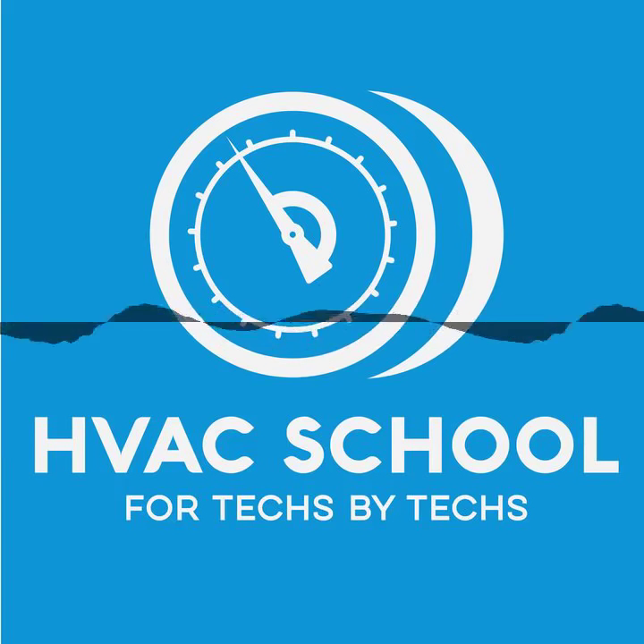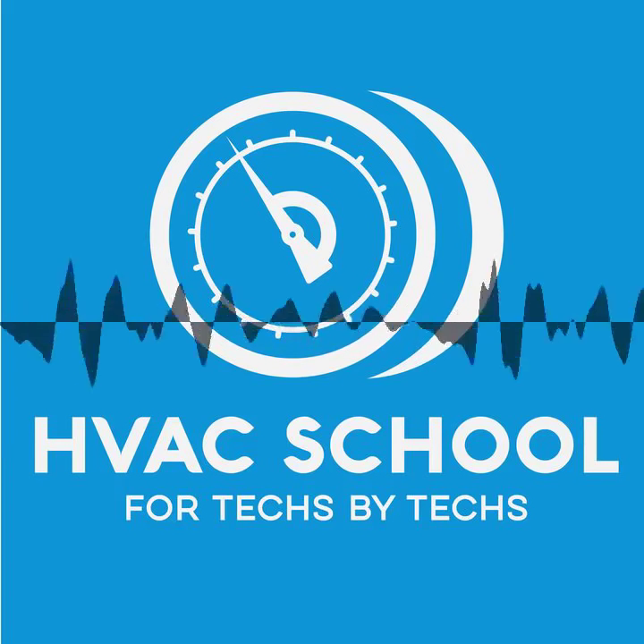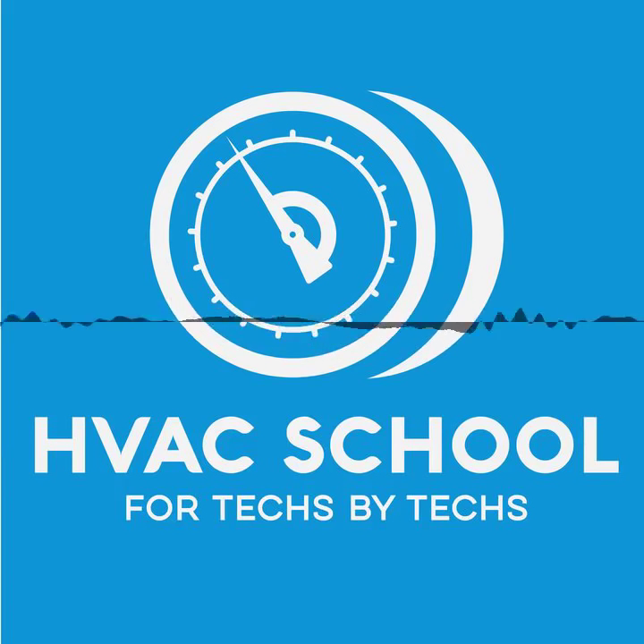We have a calculator in the new HVAC School app for Android and iOS, which you can download now, that allows you to do that calculation. But word to the wise, it is not as easy as it sounds on paper. You've got to take multiple samples in most cases, and you really have to leave that unit off for a long time so that the coil has a chance to dry out before you attempt the temperature rise calculation. Some of you are like, I have no idea what you're talking about. That's fine, don't worry about it. But for those of you who know what I'm saying, this accurate use of temperature measuring equipment, thermometers, is extremely critical when it comes to getting an accurate result with these more detailed measurements.